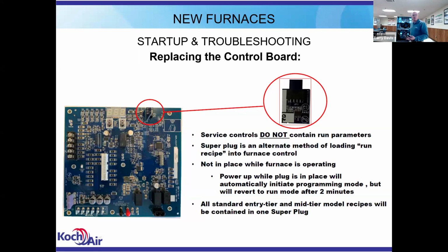It's a 3-digit number. You can use a super plug and plug it into the board, power it up, and you'll go through until you find that menu. And then you'll select that program number. Okay. Then it'll tell that board it's in this size furnace. It won't tell the board the serial number. That won't be in the board anymore. Okay. But you can set a board up that way.